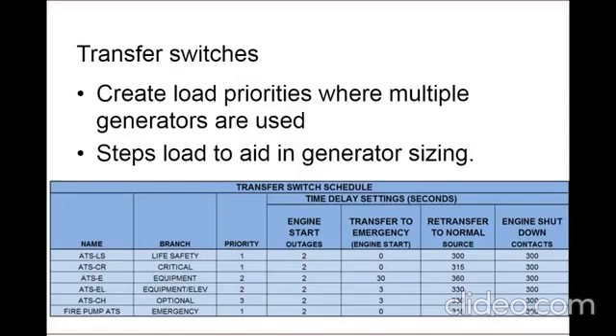Where you have a system with multiple generators, you need to plan for an emergency case scenario where you may lose one or more of your engines, but you still need to maintain your life support systems. In this situation, the life safety and the critical branches must remain functional. Therefore, you have to drop something, so the equipment switch would need to drop in order to avoid overloading the system. So here you can just see a sample ATS schedule from a project where you have more than one generator. So you want to make sure that you're identifying the priority levels of the switches and how they react upon the loss and restoration of power. And you can see here that your priority 1 branches are connected immediately to the bus once it senses power and are never shed. They are also the first to switch back once normal power is restored. And the equipment and optional branches are stepped on later to avoid overloading the system.